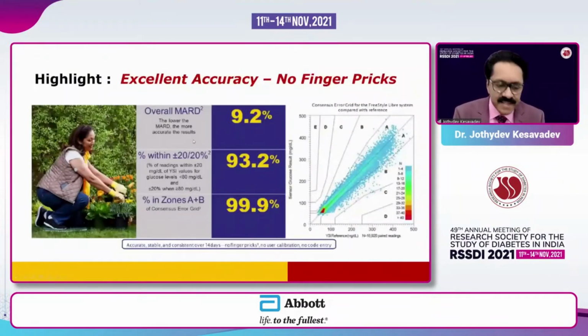What about the accuracy? This is a very often asked question. Accuracy of these devices is measured with the help of mean absolute relative difference, or MARD. So the lower the MARD, the higher the accuracy. In the earlier days, the MARD used to be 30, then 25, 20. The MARD used to be higher for type 1 diabetes for the same sensor. But on average, we have been very successful with the advancement in technologies to reach a MARD which is a single digit number, less than 10 now.